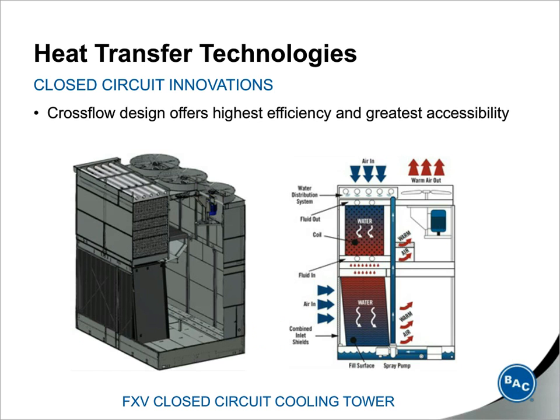Now, throughout the years, there have been different technologies for closed-circuit cooling towers that have been introduced to provide much greater thermal performance. However, before the 1990s, really the only packaged closed-circuit cooling towers that were available on the market just included a serpentine coil as the heat transfer surface. However, in the mid-90s, BAC actually introduced the first factory-assembled closed-circuit cooling tower, and that had both a serpentine coil and fill media. This crossflow design has really been the industry standard in thermal performance or efficiency, reliability, and accessibility for maintenance ever since it was released.